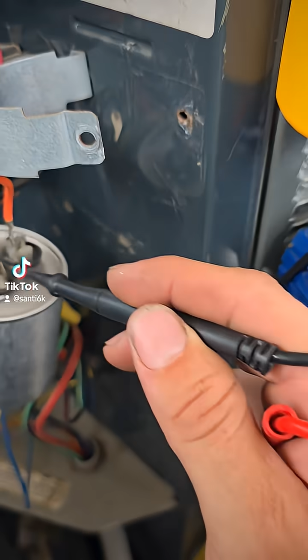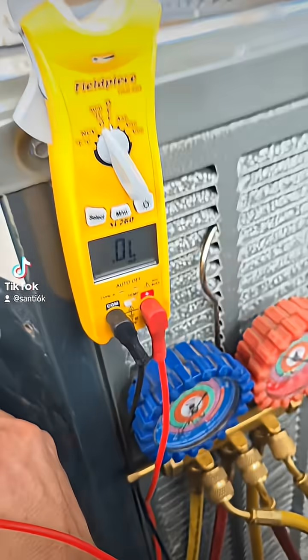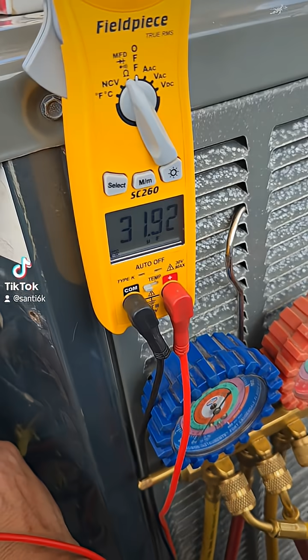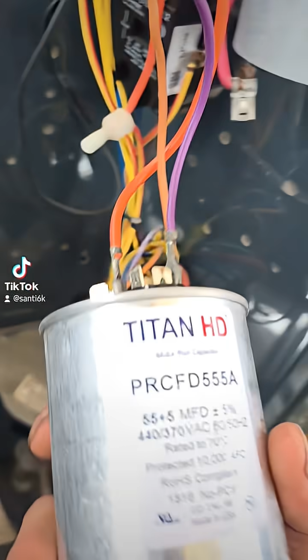Now, to test it, you're going to go ahead and check from common, which would be the power, to the compressor. So you basically put on both sides, one right here and one right here. And you want to see some kind of reading. We have 31, but this is a 55. So those are numbers that we do not want to see. So we've determined that our capacitor is the issue.